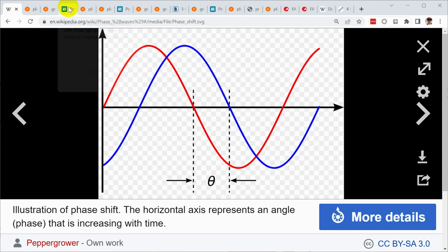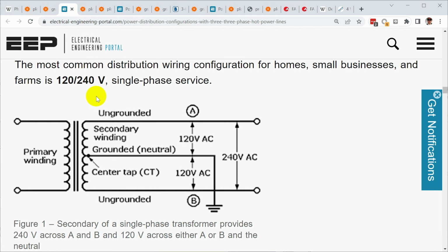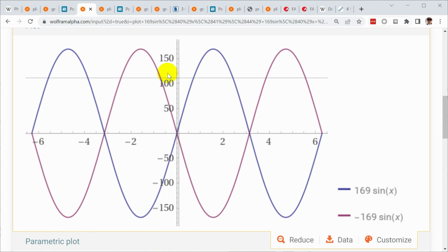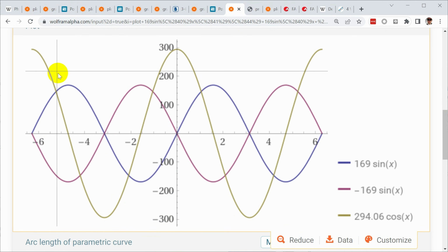It's just like what you would have seen as the output of your center-tapped home wiring. You see this, plus then you see the third leg, the wild leg, at a much higher voltage, offset 90 degrees from those two. So when you read in the forums, or see somebody in the YouTube comments say that a rotary phase converter does not produce real three-phase power with 120 degree phase separation, that's because they're measuring with respect to the neutral, and they're looking at something that looks like this.